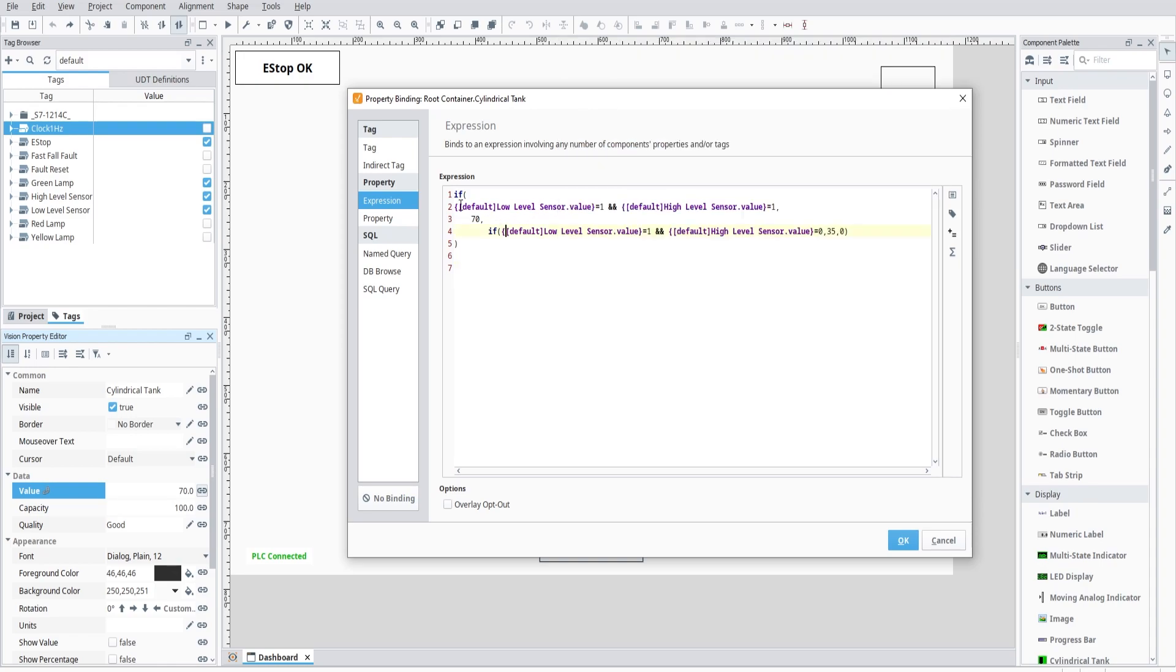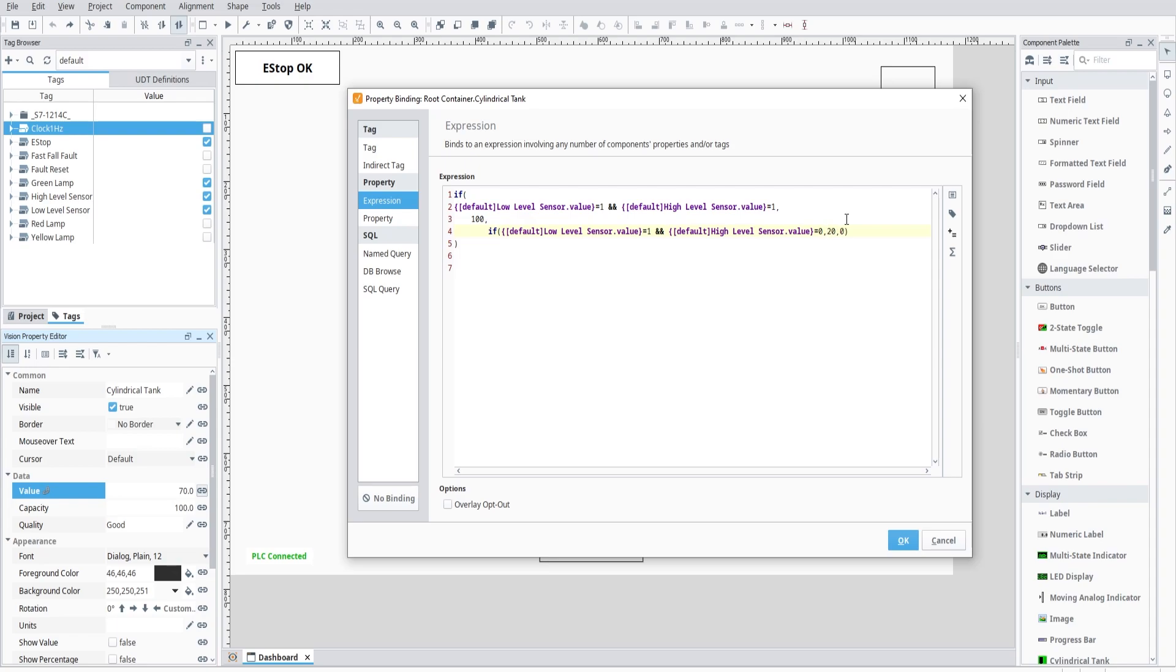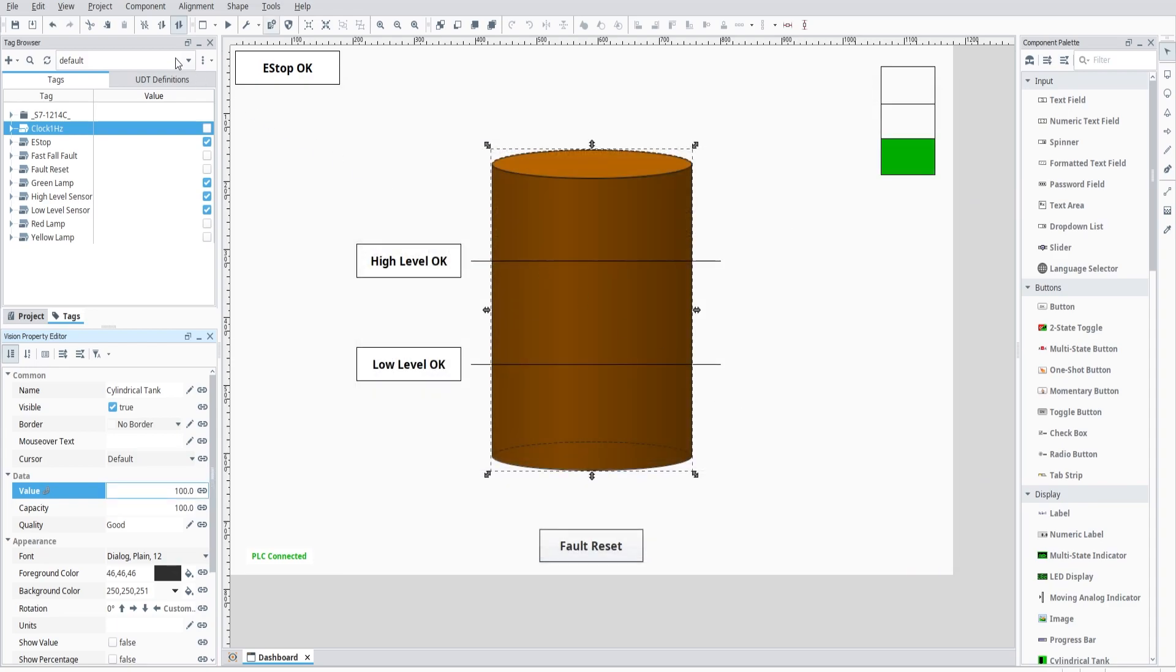So I've got if, and then my low level sensor is equal to one and my high level sensor is equal to one, then set the value to 70. I can make that for example, a hundred. And then if the low level sensor is equal to one and that high level sensor is equal to zero, then set the value to 30 or 35. And I can set that for example, to 20 even. And then if both of those are untrue, both of those are false, then set the value to zero.